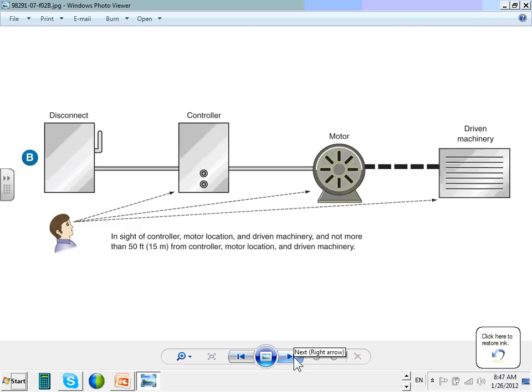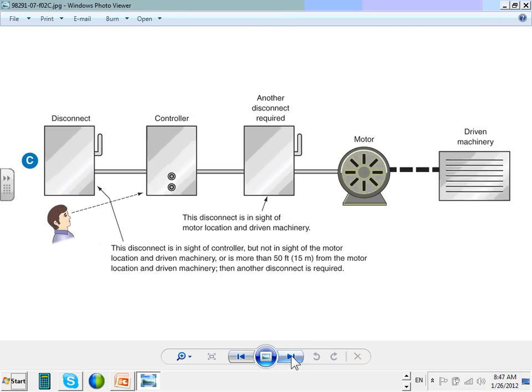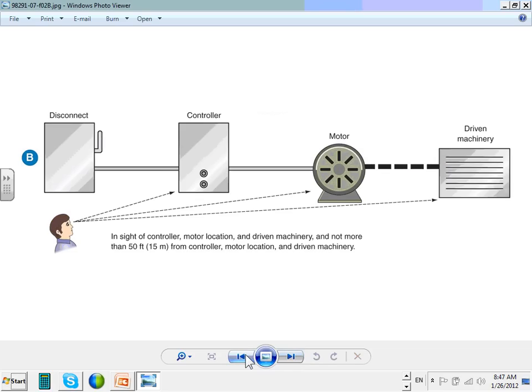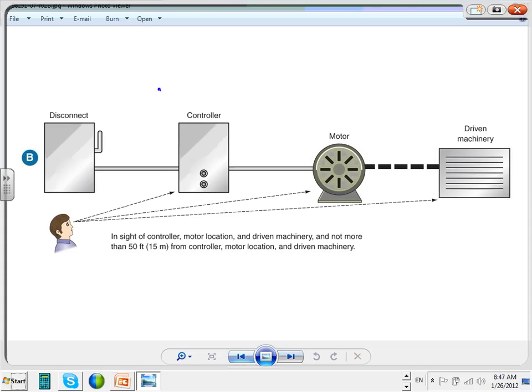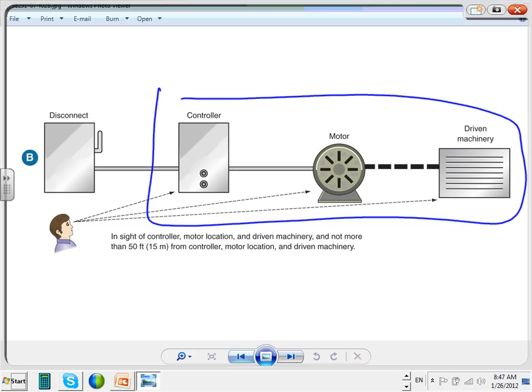Okay, so that's one thing I want to show you guys. Again, like we said, the disconnect has to be within sight of all of them, or you have to have one for each. That's the rule. This is 90% of the time. This is really one machine, and 90% of the time, a disconnect right next to them, within sight of them, within 50 feet. And this is how you should design the disconnect right to the machine.